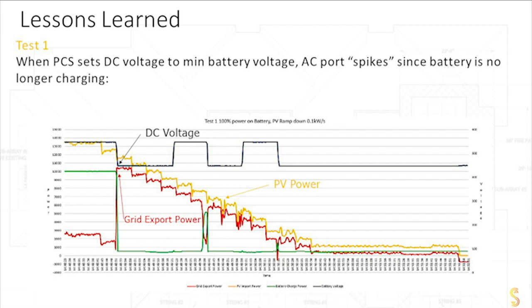So now what happens is the battery is going through a clearing time. The inverter is watching to ensure that there is enough going out into the grid so that we're not getting, again, dangerously close to zero. And it sees that. The red line came back up. There's a lot going out into the grid. And we get through a clearing window, a clearing time. And the inverter says, you know, the red line is not dangerously close to zero at all. It's exporting power. Hey, battery, you can turn back on if you want.